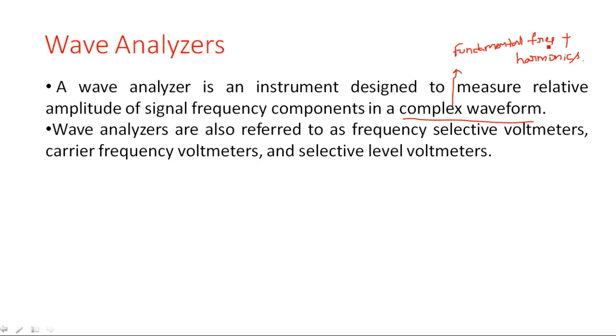Wave analyzers are also referred to as frequency selective voltmeters. We are selecting a particular frequency component and measuring its amplitude, which is a voltage — so we call it a voltmeter. Other names include carrier frequency voltmeter and selective level voltmeter.